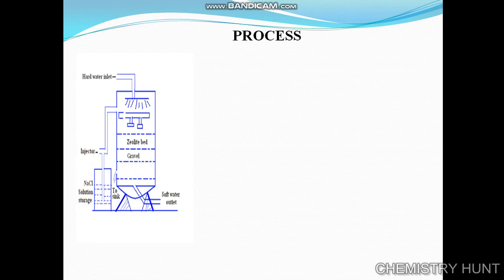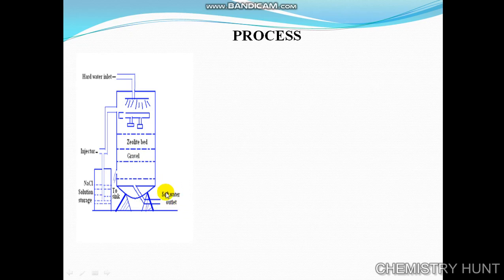What exactly happens? The hard water is first percolated at a specified rate into the zeolite bed. This zeolite bed contains sodium ions. When the hard water is passed through the zeolite bed, the zeolite absorbs all the cations present in the water. When it absorbs cations like calcium and magnesium, it gives an equivalent amount of sodium ions, so we get an equivalent amount of sodium salt in the soft water.